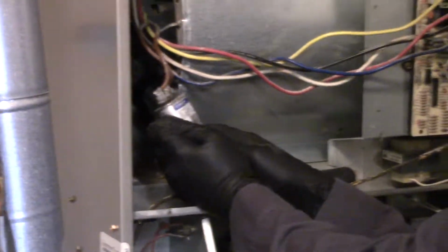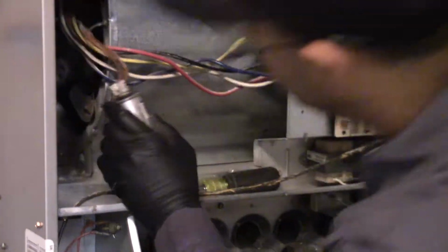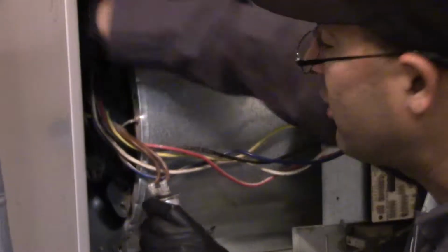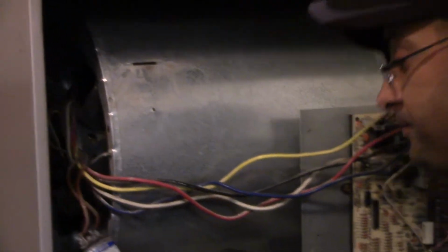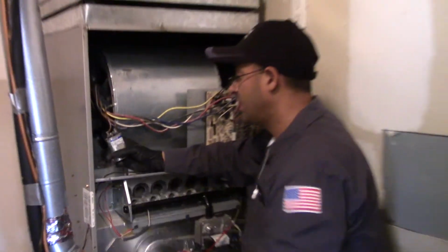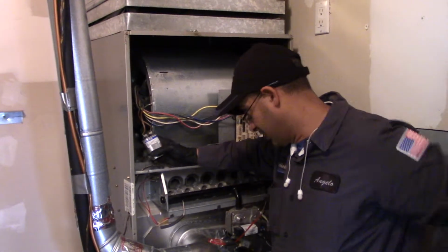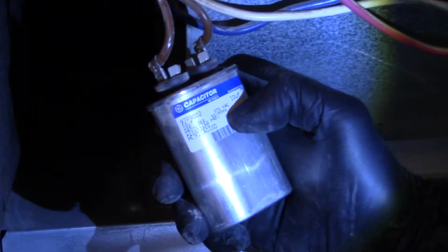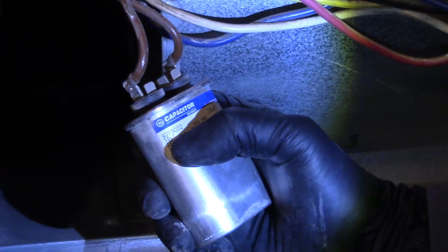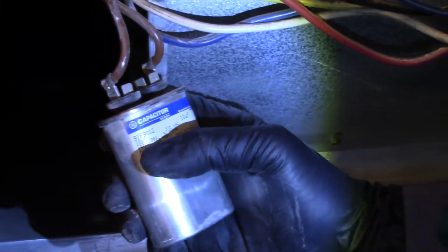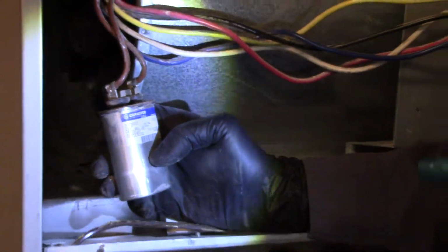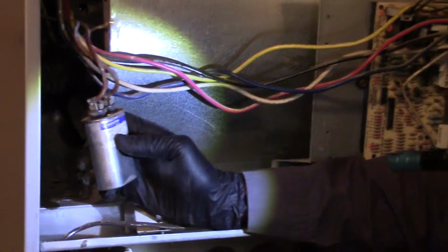But if it is the original capacitor or nobody's replaced it recently, what I'll look at is the actual sticker on the motor—it'll tell me what size capacitor it needs and what voltage. If you look at this sticker closer, it says this capacitor is 370 volts and 10 UF, plus or minus 6%. I know that this system is only a 120 volt system, so this capacitor would definitely handle it.